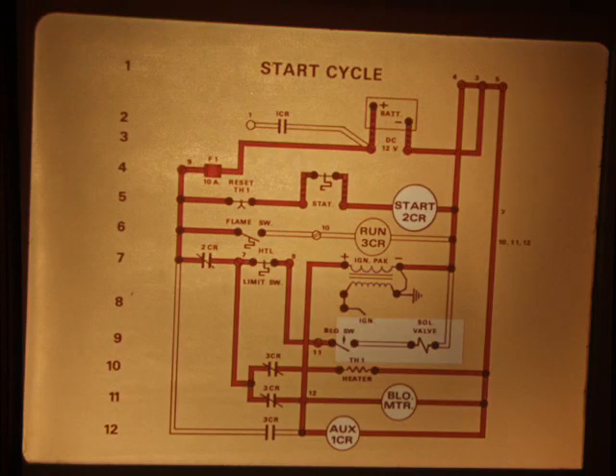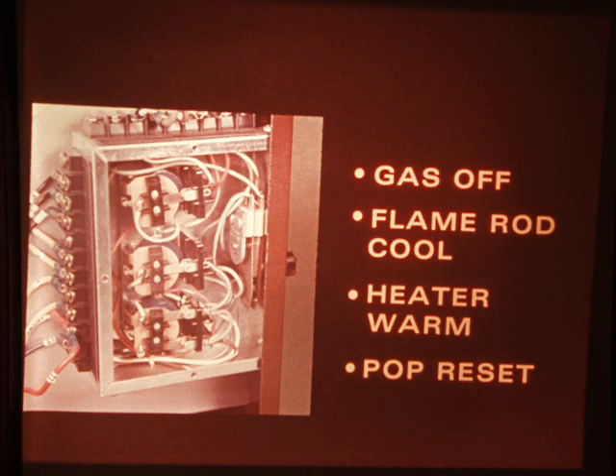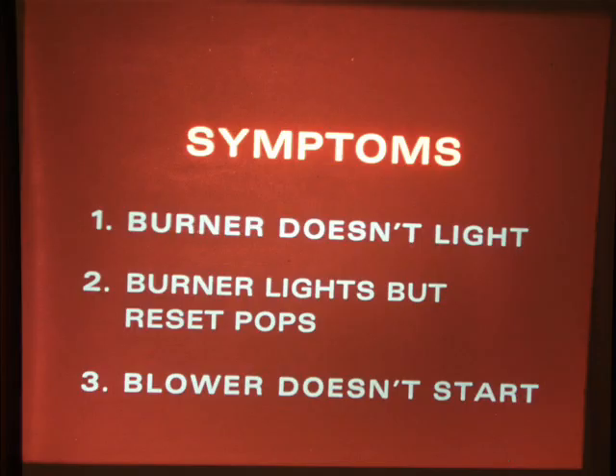Incidentally, the same thing will happen if the input voltage is low or the blower runs slow for any other reason. The centrifugal switch will open, the gas will shut off, the flame rod will cool and open the run relay, and the thermal heater will warm up and pop the reset. With that in mind, let's see what to do.